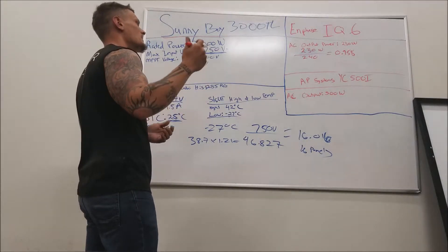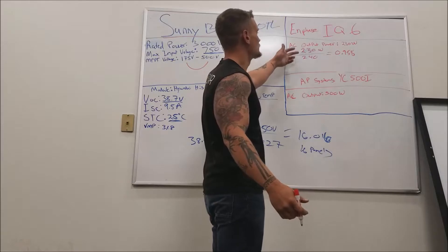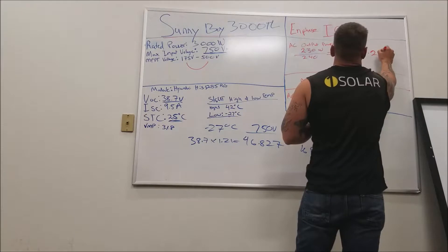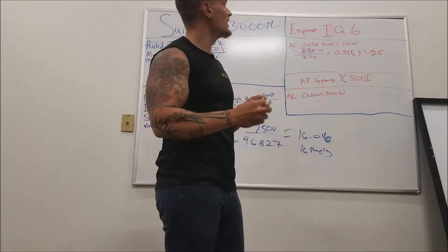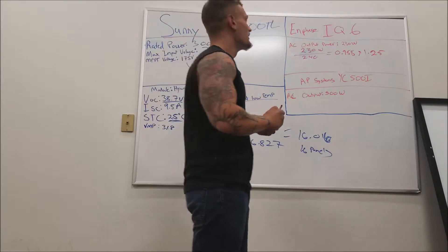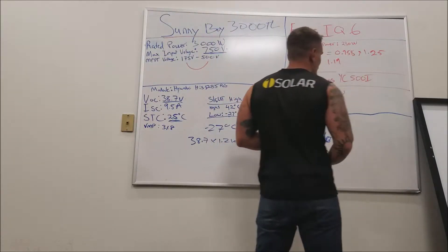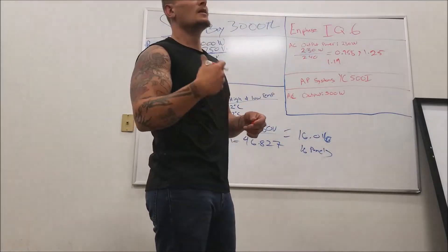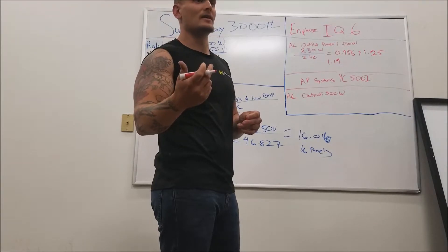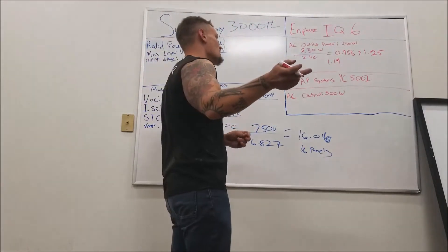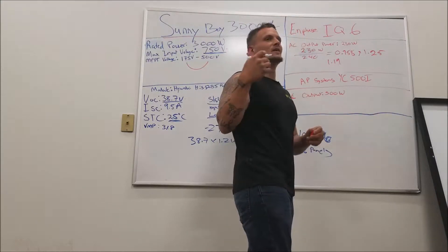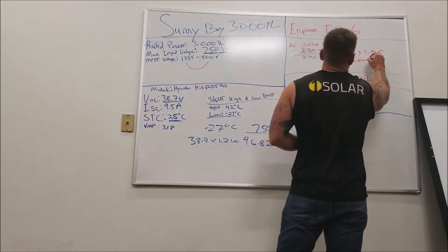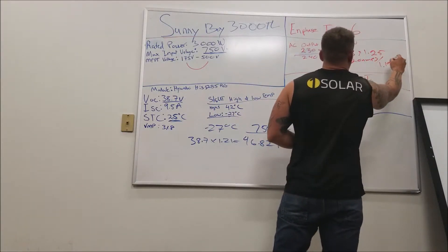So that's 0.958 amps, and then we need to multiply by the continuous current factor — 0.958 times 1.25 equals 1.19 amps continuous current. We're using an Enphase system with 12-gauge wire. NEC 240.4 tells us with a 12-gauge wire we need to use a 20-amp overcurrent protection device, so we need to stay under 20 amps. We take 20 amps and divide by 1.19 amps.